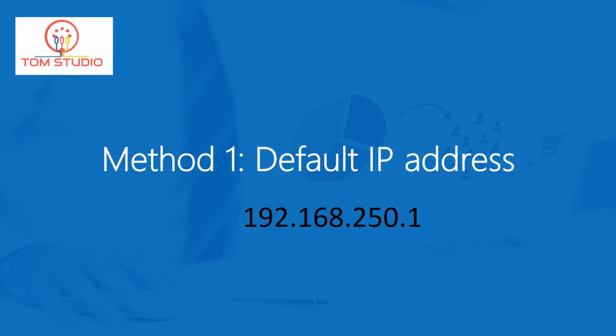For both C-series PLCs and NX-series PLCs, no matter whether it is the CPU built-in Ethernet port or an Ethernet module, all have a common default IP address, 192.168.250.1, so it is definitely worth trying the default IP address. However, if you are working on a customer site, you might forget about this way because 9 out of 10 customers or system integrators will change this default IP address setting, otherwise, it might be too easy for hacking.